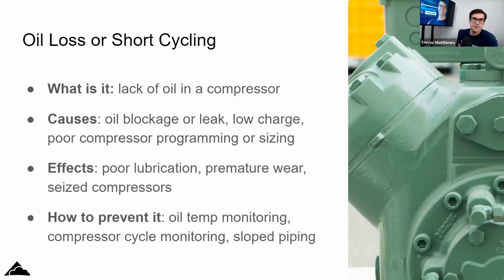Yeah, so every time a compressor starts up, there's something called oil carryover rate. When it starts up, there's a lot of pressure, and it'll shoot out a little bit of oil. So you need your compressor to run for a certain amount of time to move the oil through the system to get it back. If it starts up, shoots some out, and shuts off, you don't have the run time to make that oil travel with the vapor, because it's way harder for oil to travel with vapor than with liquid. You need it to travel all the way through the system and back. So if you start up, shut off, start up, shut off, you keep shooting out little bits of oil until you don't have enough runtime to make it come back. And really, that's how it works.